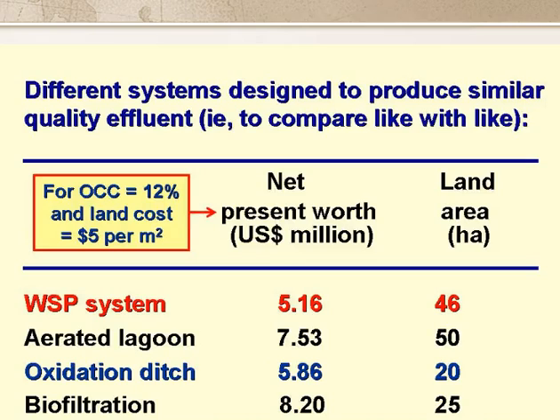What Arthur did next was to compare the cost of the four systems in net present value, or net present worth, terms. Ponds were the cheapest on an NPV of just over 5 million US dollars. The next cheapest was the oxidation ditch at just under 6 million dollars, and the other two were more expensive. The figures in the table are for a discount rate of 12% and a land price of 5 dollars per square metre.